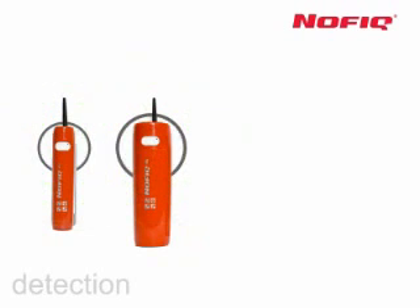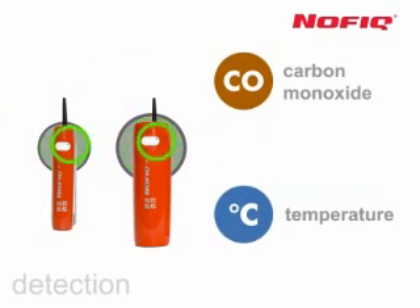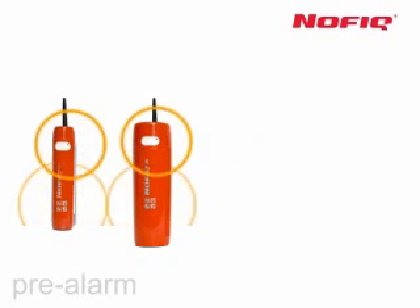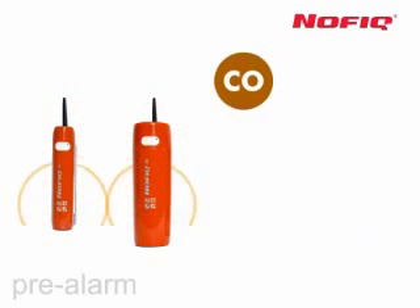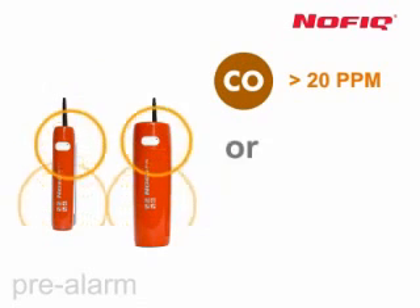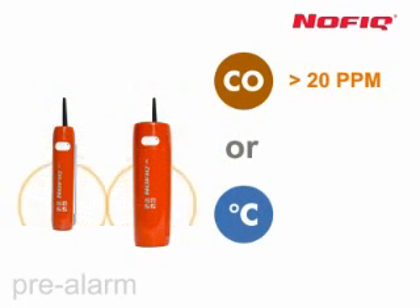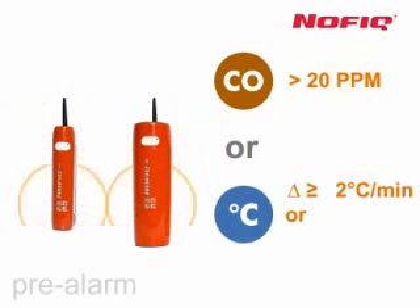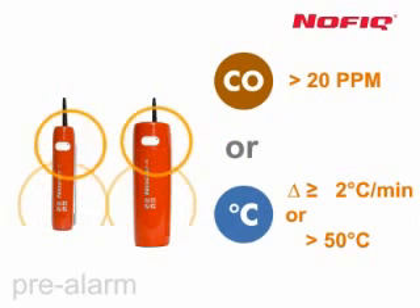Every second, the NOFIQ 20 and NOFIQ 80 use extremely reliable carbon monoxide and temperature sensors to check the predetermined safety margins. If preset limits are exceeded, the system will go into fire alert mode and, if necessary, into fire alarm mode. Fire alert mode is triggered if the carbon monoxide sensor measures 20 ppm or more, if the temperature sensor detects an increase of 2 degrees Celsius per minute, or if the temperature reaches 50 degrees Celsius.